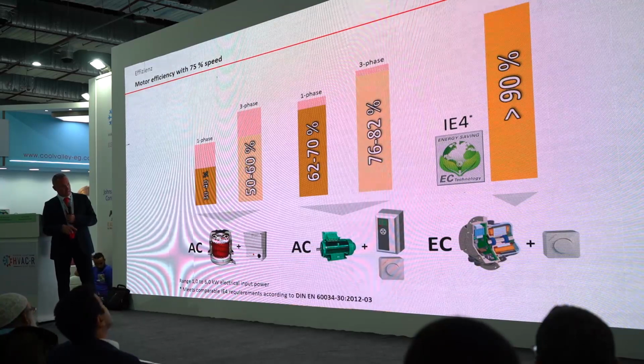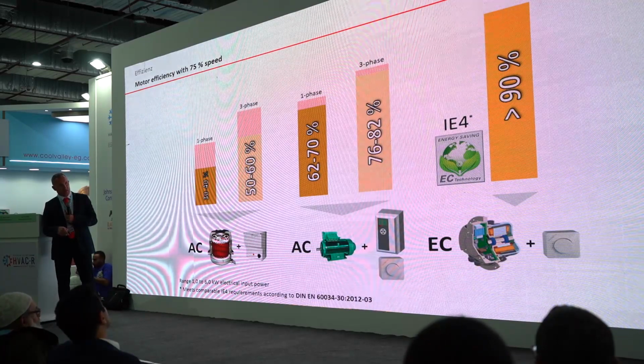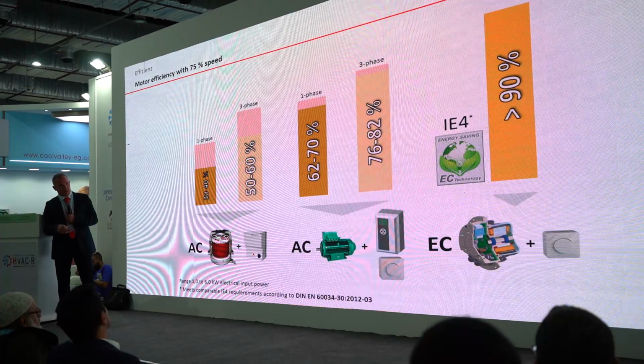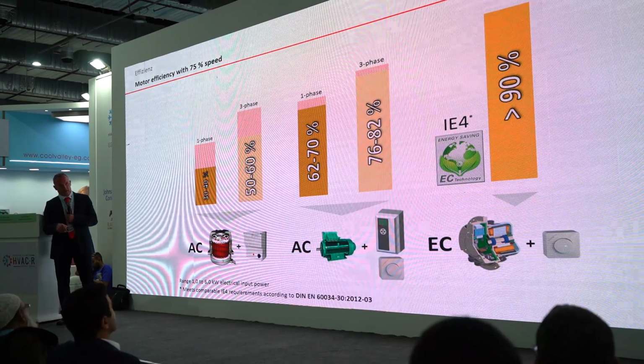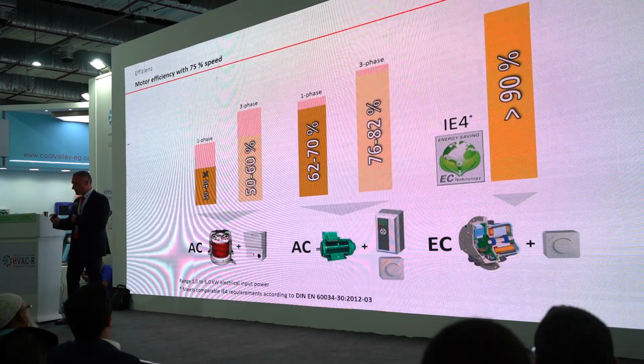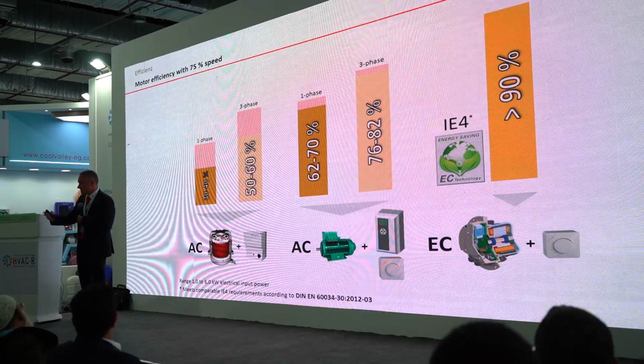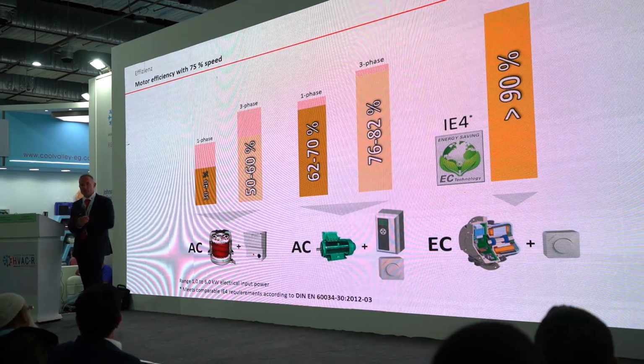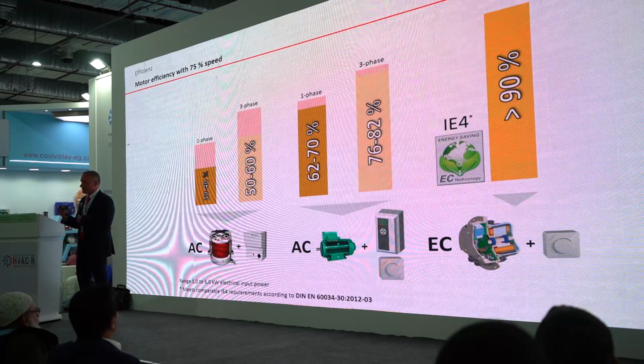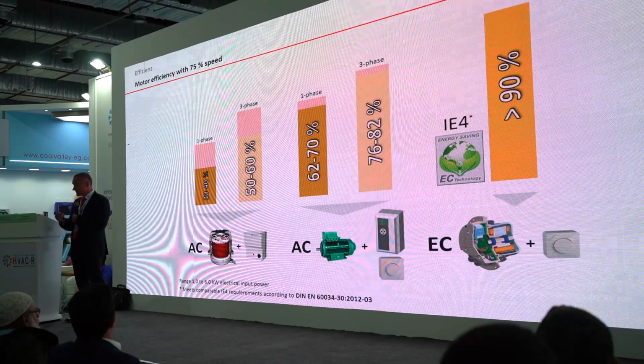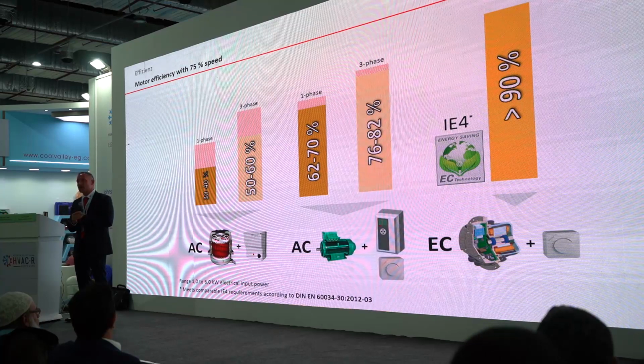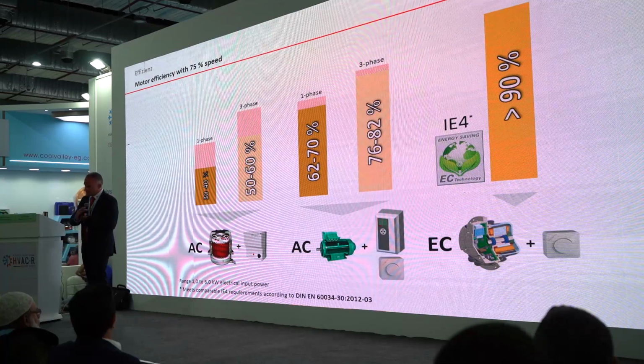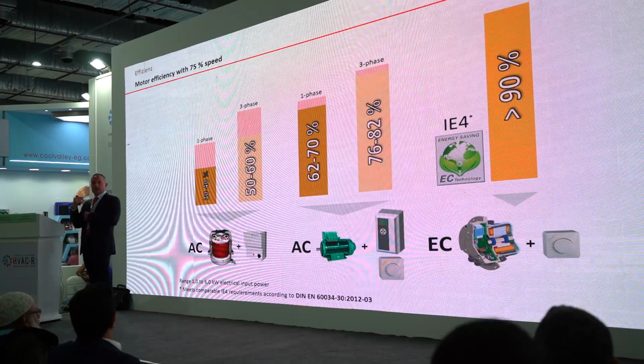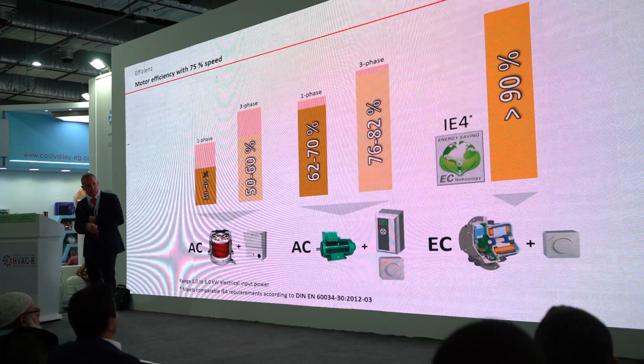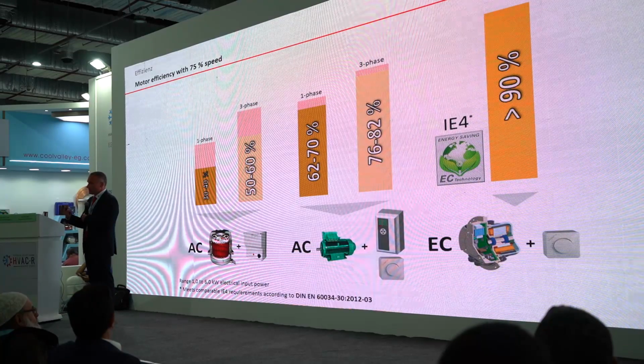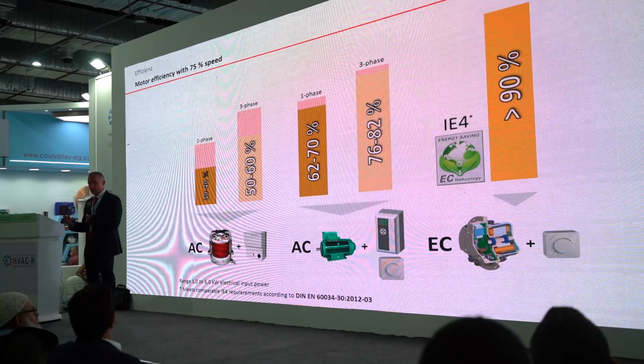At the bottom, if you want to control an EC motor, there's no VFD needed. This is the potentiometer, giving the signal to the motor. This is the easiest way to control an EC motor. As an option, we have different kinds of control units. If this 0 to 10 volt signal is not coming from the building management system, if there's no BMS available, we can install a potentiometer or our small device to control the EC motors.